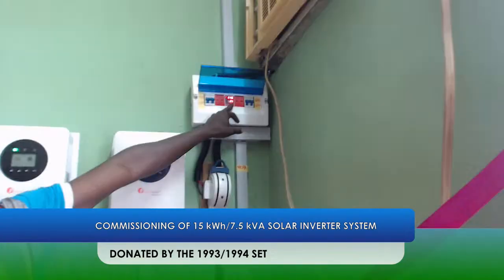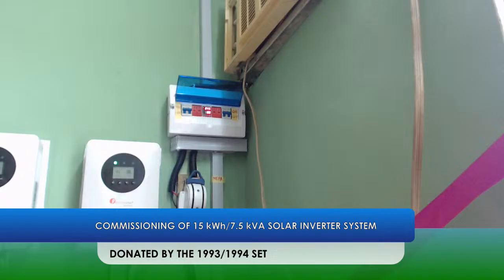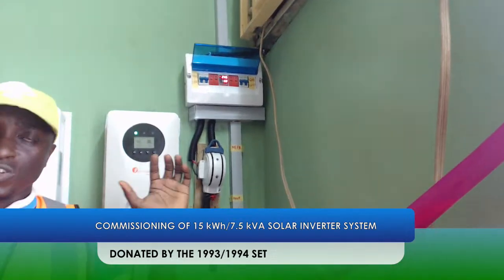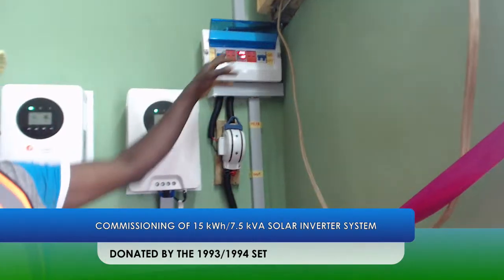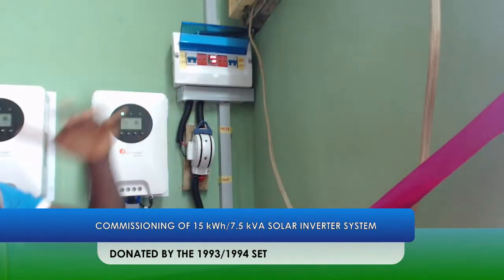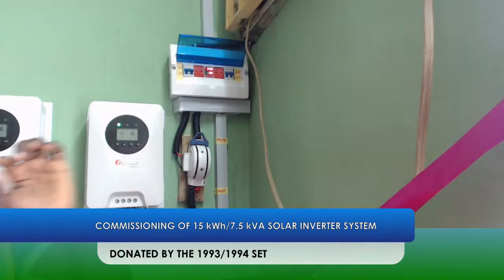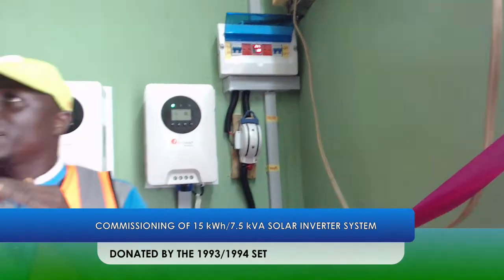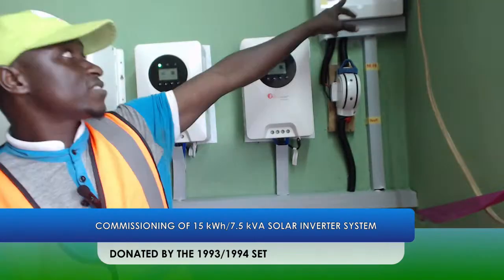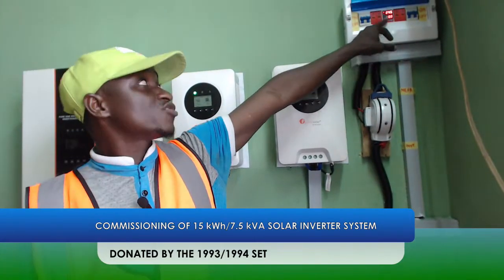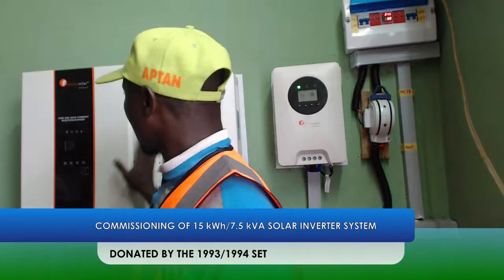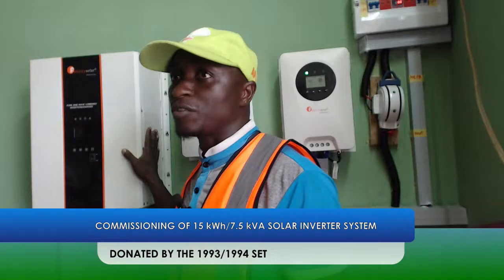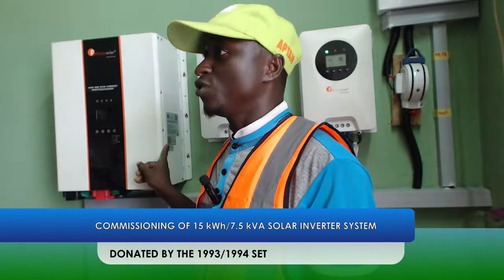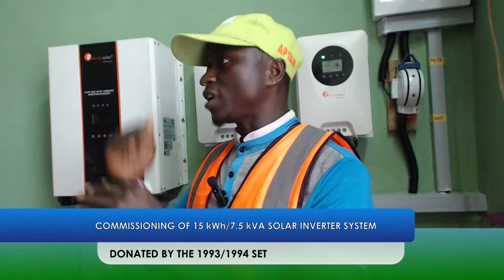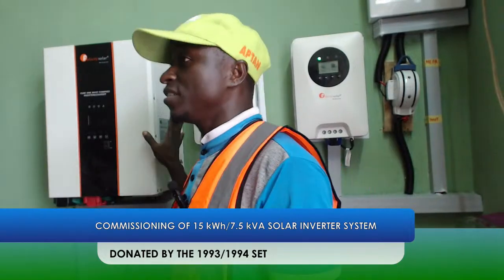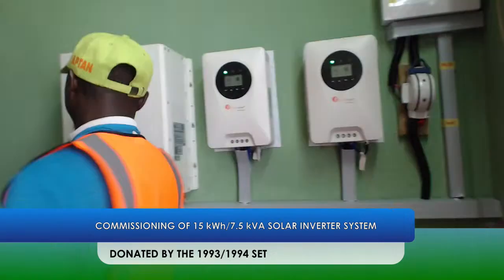So this is the AC voltage monitor. It monitors voltage from the supply authority, they call it NEPA. Once set to the range, we set it to 240 as input, any upsurge and it will trip off. As you can see, this is 245, so it has tripped off. It doesn't supply the inverter again because that can damage the system. Once the voltage is back within range, it can supply the inverter again in order to protect it. So now, how does it work?